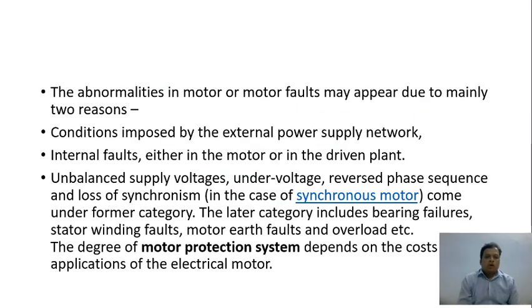The abnormalities in a motor, or motor faults, may appear due to mainly two reasons. One reason is conditions imposed by the external power supply network, and the second is internal faults either in the motor or in the driven plant. Unbalanced supply voltages, under voltages, reverse phase sequence, and loss of synchronism come under the former category. The latter category includes bearing failures, stator winding faults, motor earth faults, and overloads, etc. The degree of motor protection depends on the cost and application of the electric motor.